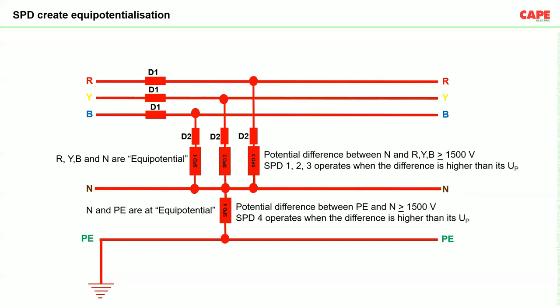Now, the whole thing which has happened here has to happen in a very short duration, let's say a few nanoseconds, because in an earlier slide, we have seen that a normal switching surge will be in your system for 28 microseconds. So we need a device which reacts faster than 28 microseconds. Hence we use an SPD which has a response time of a few nanoseconds. 1 nanosecond is the best response time we have, and it can be 25 nanoseconds as well. So this is how a normal SPD operates.